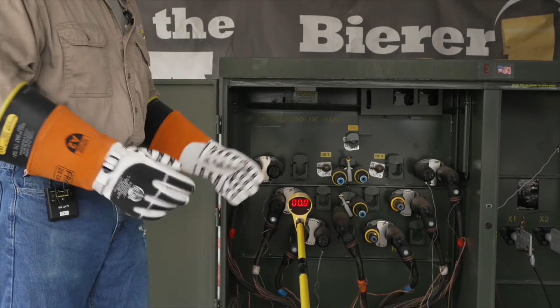Remember, that's your best friend. So now we go to that conductor, long source, point source, whatever it's called, and we make that contact. So we have test, open, test. The tool you're going to use is accurate enough to verify an absence of nominal voltage, because OSHA says so.